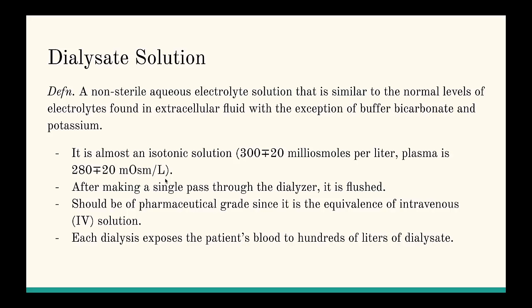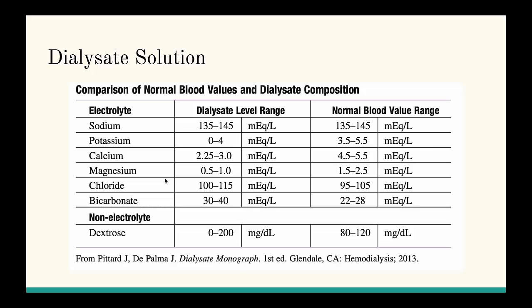And one thing also to keep in mind is how much product is used to filter out someone's blood. Each dialysis exposes the patient's blood to hundreds of liters of dialysate. That's how much is necessary to take out those waste products that we don't want. So here I put a table that I found in a book, and here it talks about what are the materials that are inside the dialysate. You see your sodium, potassium, calcium, magnesium, chloride, bicarbonate. We're going to be going into more detail about this part because this is an important component of the dialysate fluid. It actually balances the pH levels.